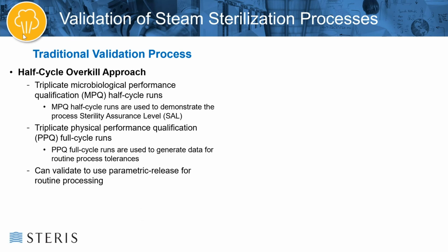so that you know that if you do a full cycle, you will have a process that's twice as efficacious as that. And then after you get done with your MPQ runs, you'll run a series of physical performance qualification runs. And these runs are typically used to generate process data for routine process tolerances, so that when you're validating a process, you know from your validation results that during actual production processing you have to have this amount of exposure time at this certain temperature, and no more than that or no less than that. We started also talking about temperature and pressure rates of change and different aspects that impact lethality that we didn't get into previously. So the PPQ runs are done to generate those tolerances.